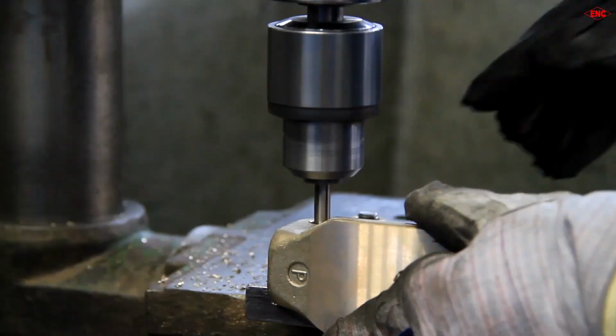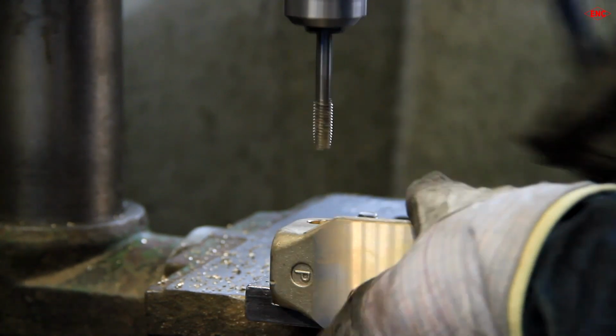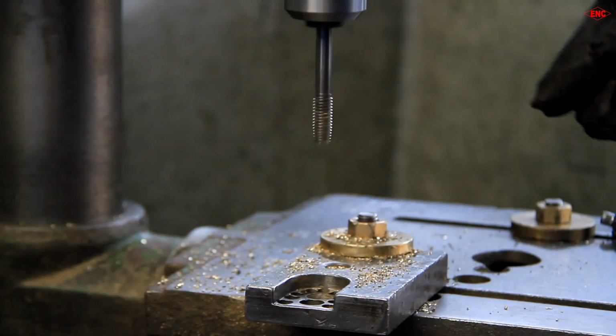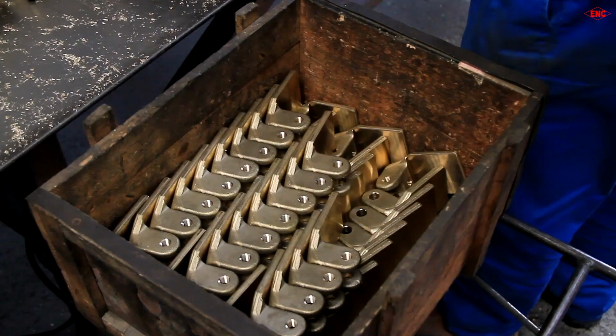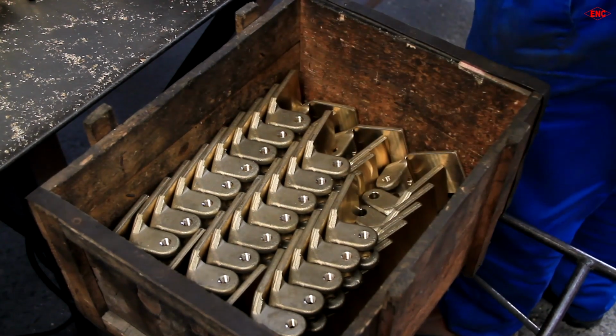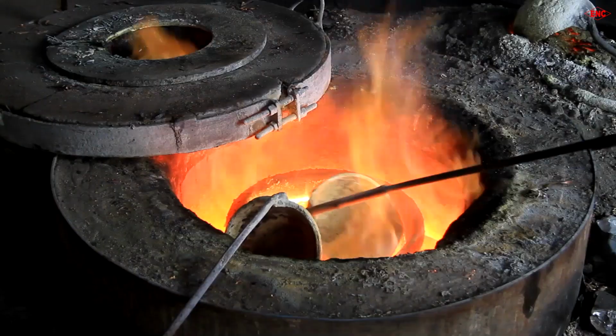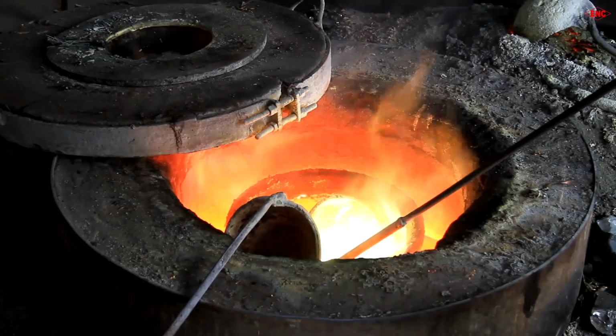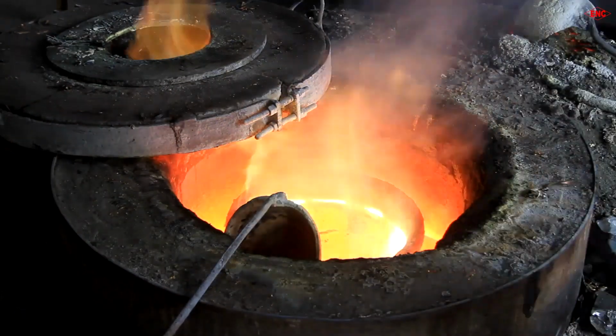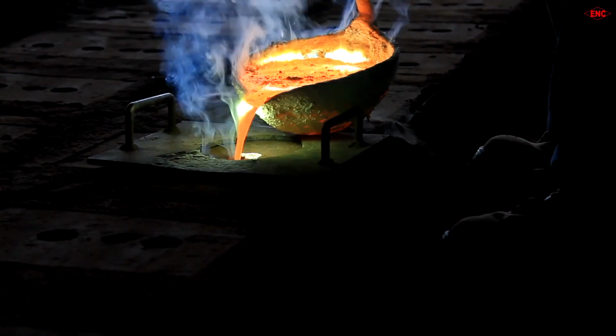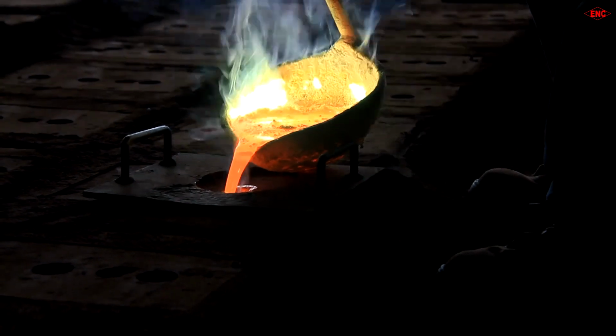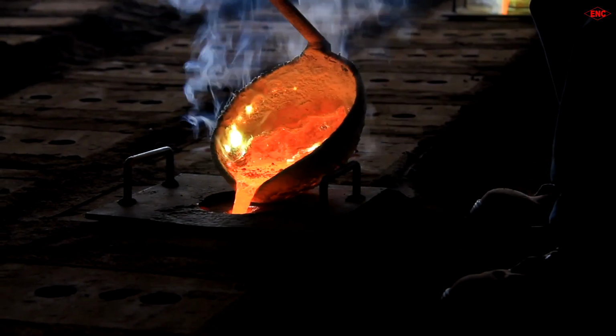The transformer bushing is the insulation bushing that leads the high and low voltage leads inside the transformer to the outside of the tank. It not only serves as the ground insulation of the lead, but also fixes the lead. The transformer bushing is one of the current-carrying elements of the transformer.